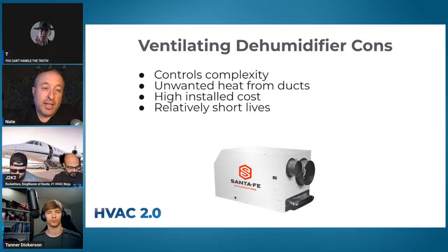On the con side, the controls add complexity, and that's been a consistent frustration. Unwanted heat can come from ducts, because the dehu runs when the air conditioner isn't, so you get warm air coming out of the vents in the middle of summer, which people don't like. It's also a high installed cost—these aren't inexpensive, and they have relatively short lives compared to HVAC equipment if you put a new system in.